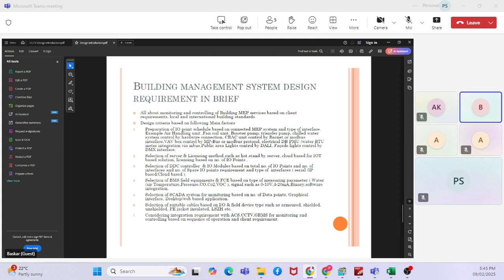In the design criteria, we develop an IO point schedule based on the MEP system we interface with - for example, air handling unit, fan coil unit, booster pump, transfer pump, chilled water, multiple systems, and CRAC units for IT rooms. These are connected through the BACnet or Modbus interface. When we design the system and list the equipment we need to monitor and control, we also need to define the interface, whether it's a hardware interface or a software interface.